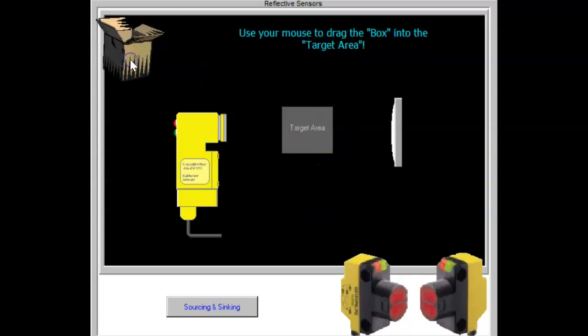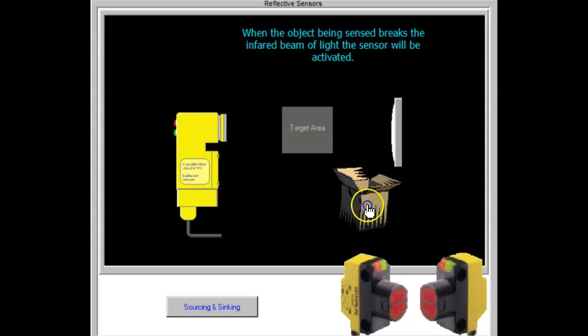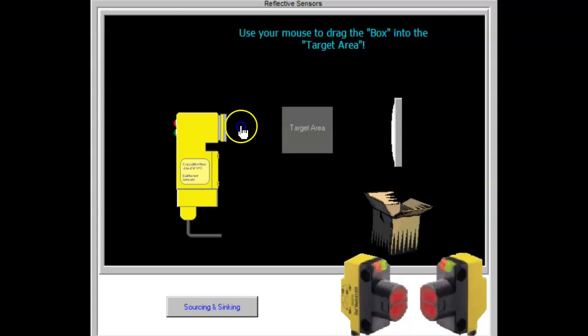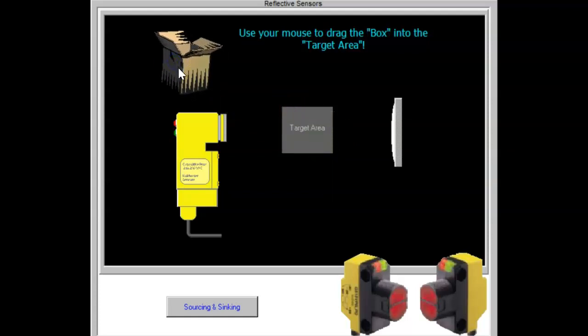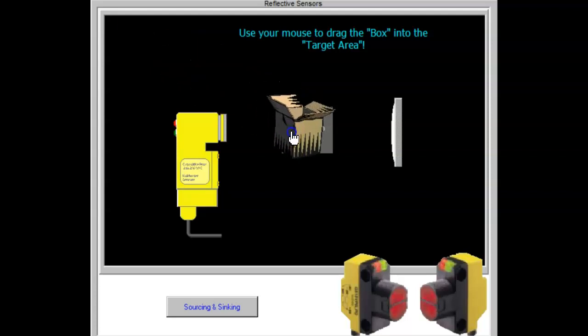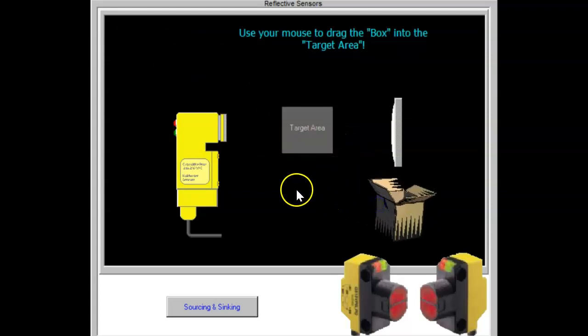Retroreflective scan has the light source and the photoreceiver in the same sensor body. This is often referred to as a retroreflective scanner. The beam of light is directed at a retroreflective target, acrylic disc or tape, which returns the light beam along the exact same path that it was sent. A larger target reflector will return more light to the photosensor, allowing increased scanning distance.